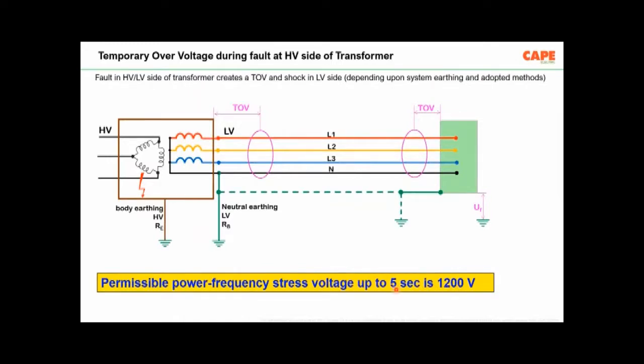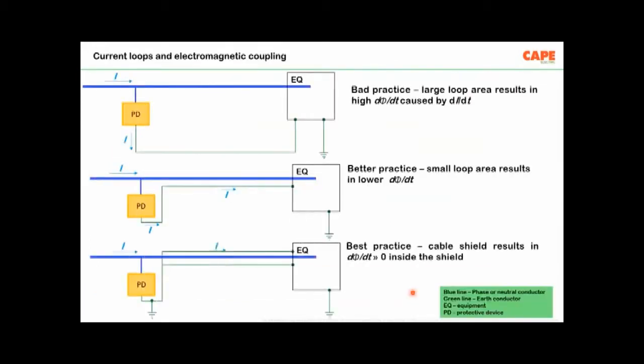That means every electrical equipment connected to the electric mains supply from the transformer is supposed to withstand 1200 volt up to 5 seconds. But whether we are really doing it is a second question. Similarly, whenever an electrical installation is made, one of the important safety measures to be included is reducing the current loop. The best practice is you should route all your conductors at the same place, the same route, as shown in this particular picture. If you have a large loop, as in the first picture, it may create a lot of additional problems. Basically, you lose the safety.